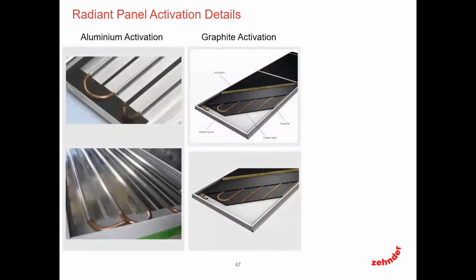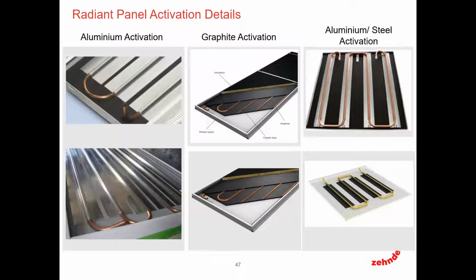All right, so I keep talking about activation and what is this activation and what does it mean? Well, the activation itself, depending on the manufacturer, depends on what type they use. Manufacturers will use aluminum extrusions on the backside of the panels or graphite, and some even use steel. But really, when I say activation, what the activation is the means on the side of the panel that gets the energy from the tube to the face of the panel. Because overall, the higher the average surface temperature, or lower, depending if we're talking about heating or cooling, is what drives your BTUs per square foot. So if you can get a higher or lower BTU per square foot or a surface temperature, you're going to get more performance out of the panel, and the panel is going to react faster when it heats up or cools down. So the activation is really what drives the capacity of the panel.